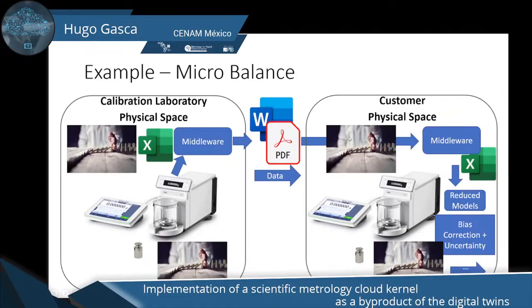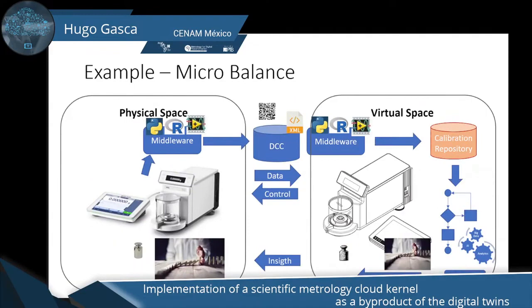who must read the certificate, interpret this calibration certificate, and then through a middleware software uses it with new measurements, which they also need to use with a device measurement, and they use reduced models in order to correct bias and calculate the uncertainty of their measurement when using information that comes from a digital certificate. So there is a chain here that continues and goes on to their users. So this is a common scenario prior to digital transformation or automation. So now how does this work here?